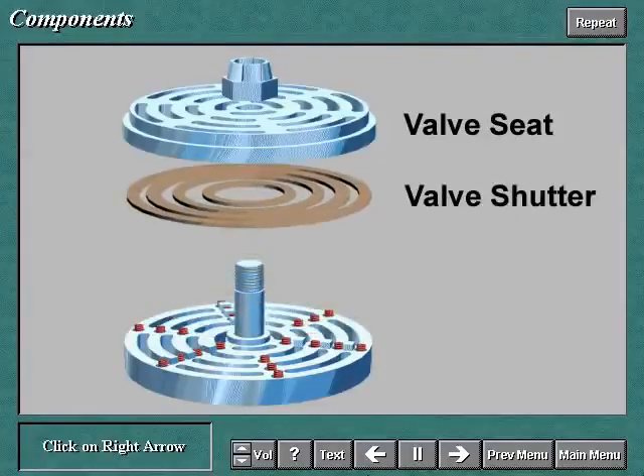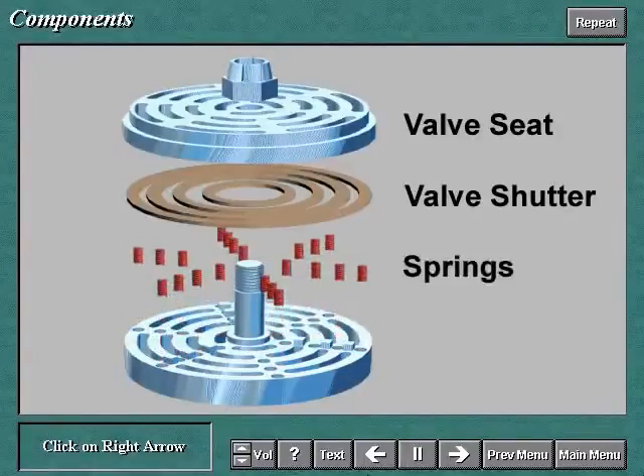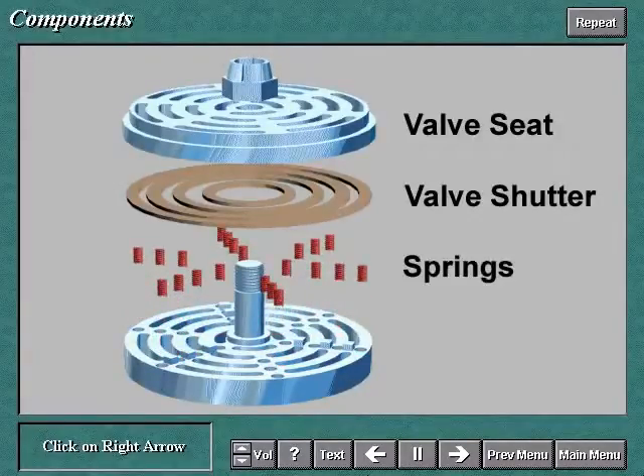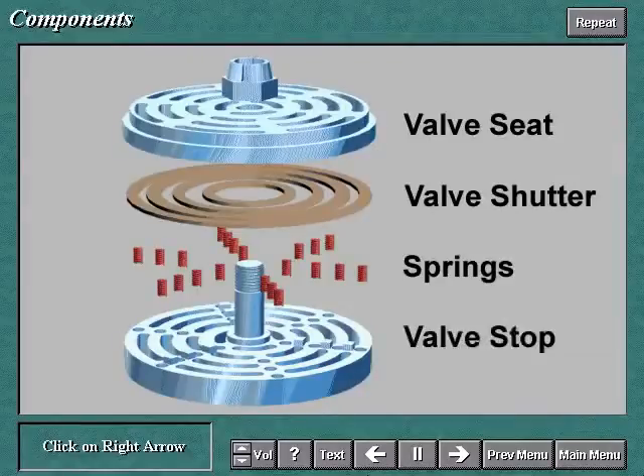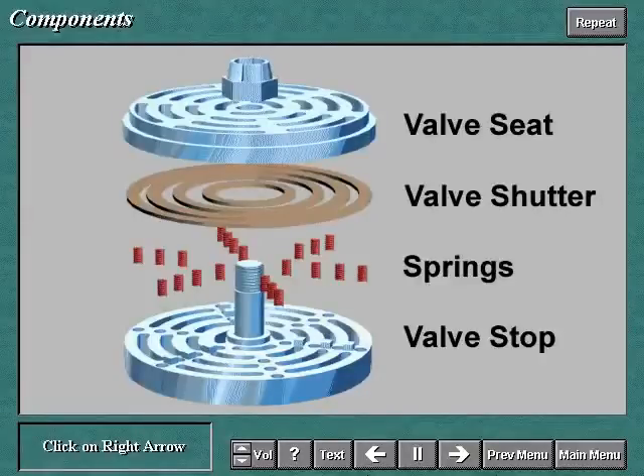The valve shutter is the component that alternately opens and shuts the flow ports. The springs are the components that return the valve shutter onto the seat when the flow of gas has stopped. The valve stop, or guard, is the part against which the valve shutter stops. It determines the degree of lift that the shutter may have.